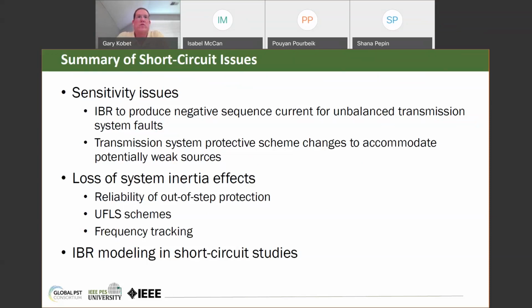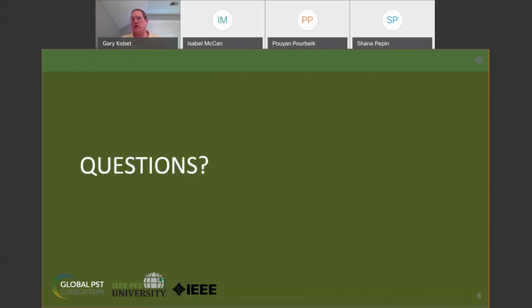The best case is that we have adjustments to the inverter-based resources themselves, and that's one of the things that P2800 is trying to do, is require a certain characteristic negative sequence response for unbalanced faults, along with changing the transmission system schemes so that we can actually detect faults reliably. Loss of system inertia effects, and we talked about out-of-step protection, swing rates, and then rate of change of frequency and those effects. And then IBR modeling and short circuit studies. And that is my part. So I took roughly 30 minutes. So Isabel, I'll turn it back over to you.